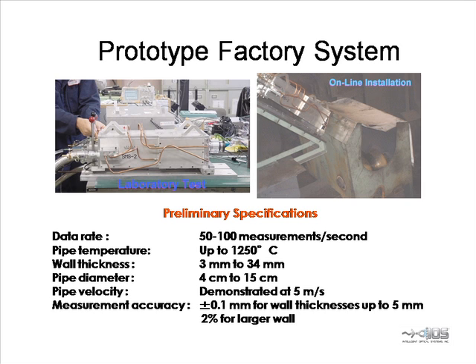The left photo shows the measurement head being assembled in the lab. The head has provision for water cooling and an air purge. The right photo shows the head mounted in position on the line, in this case at 45 degrees. Note that measurements can be made on tubes at a temperature above 1000 degrees and moving 5 meters per second.